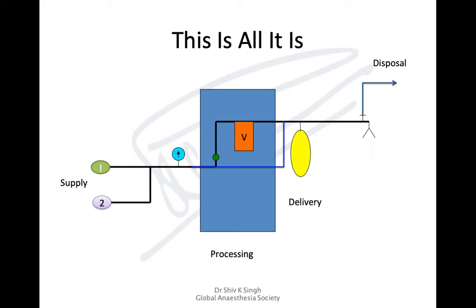The oxygen can also come from cylinders at the back of the machine. Once the oxygen supply comes in, it is processed by the machine, then delivered to the patient via a breathing system. Waste gases are disposed of using scavenging. So there is supply, processing, delivery, and disposal — this is known as the SPDD model.